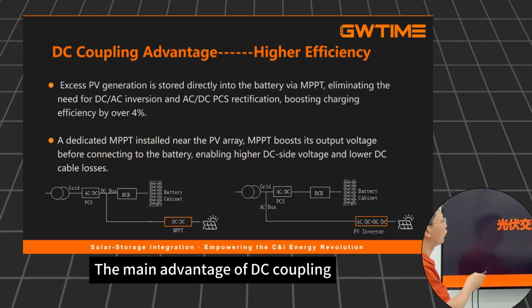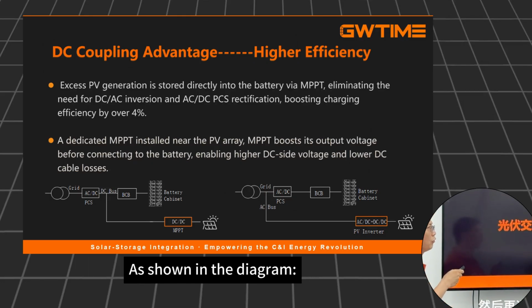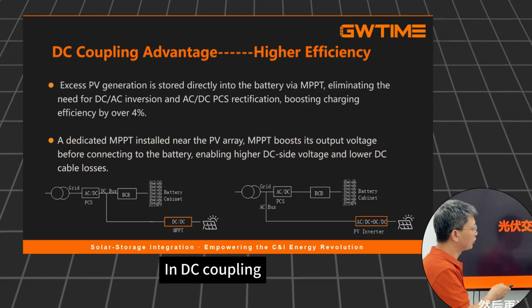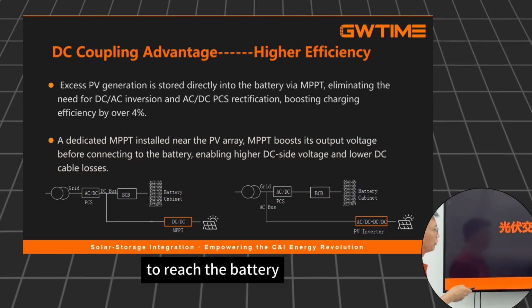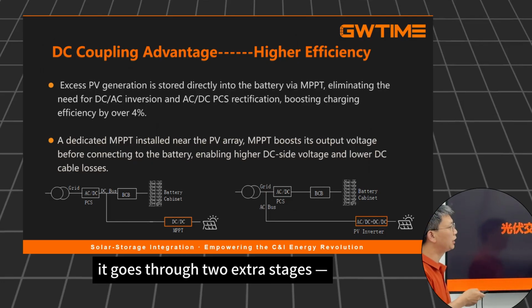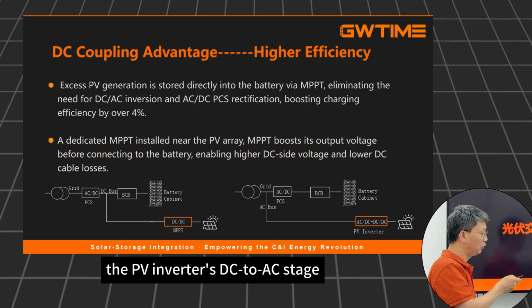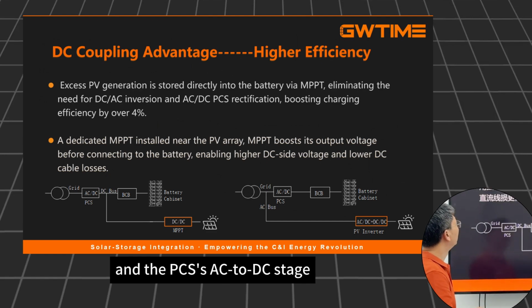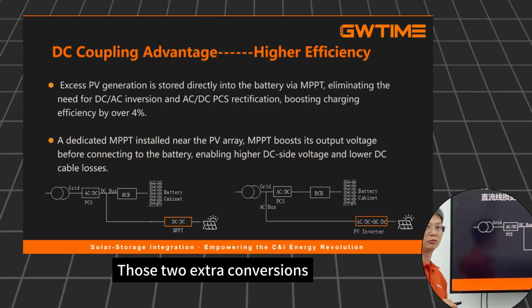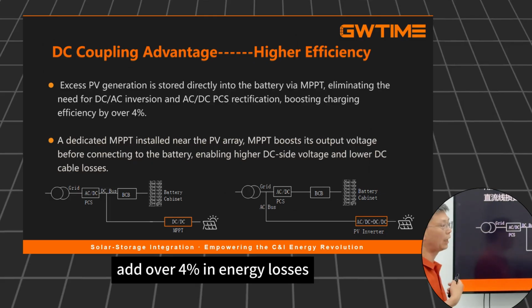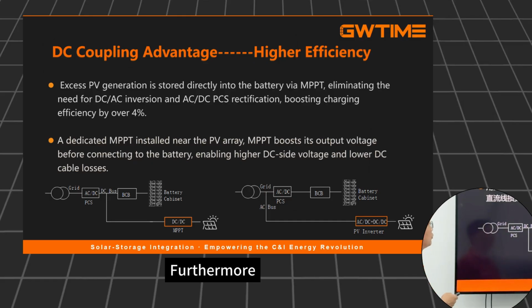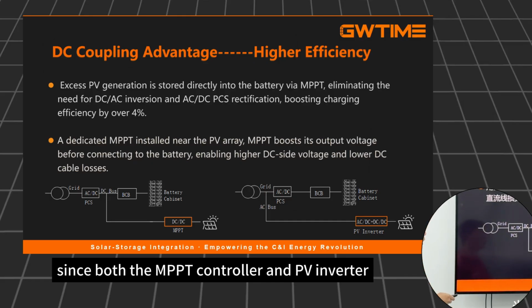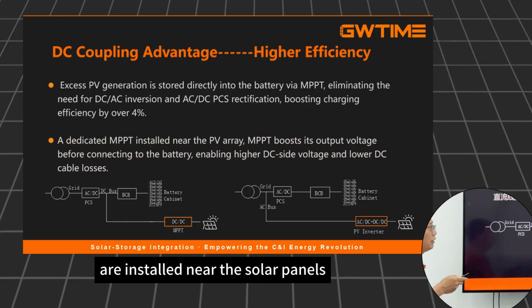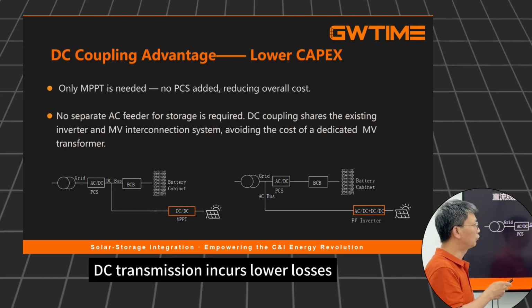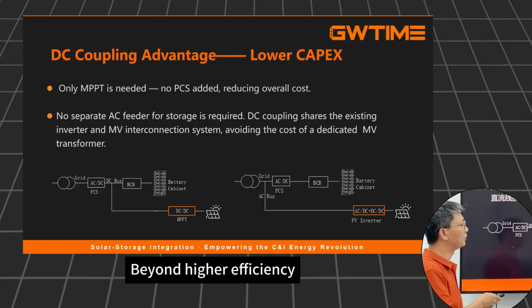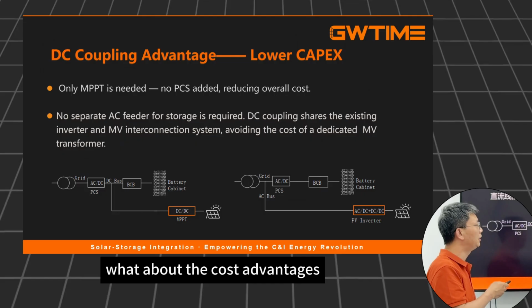The main advantage of DC coupling is higher charging efficiency. As shown in the diagram, in DC coupling, energy goes through only one conversion stage to reach the battery. In AC coupling, it goes through 2 extra stages, the PV inverter's DC to AC stage and the PCS's AC to DC stage. Those 2 extra conversions add over 4% in energy losses. Furthermore, since both the MPPT controller and PV inverter are installed near the solar panels, DC transmission incurs lower losses than AC transmission. Beyond higher efficiency, what about the cost advantages of DC coupling?